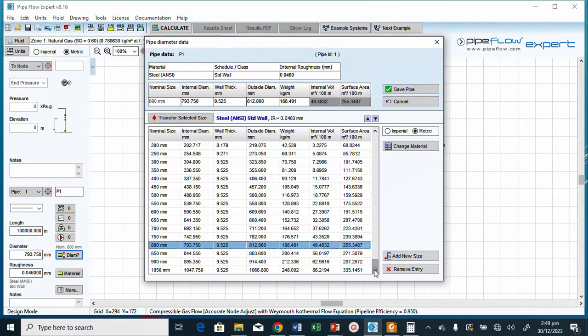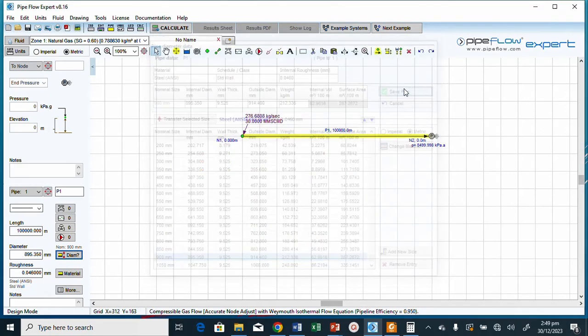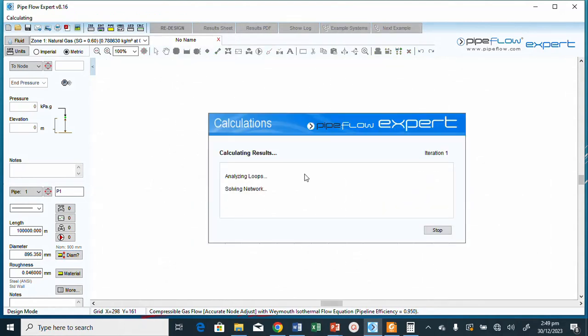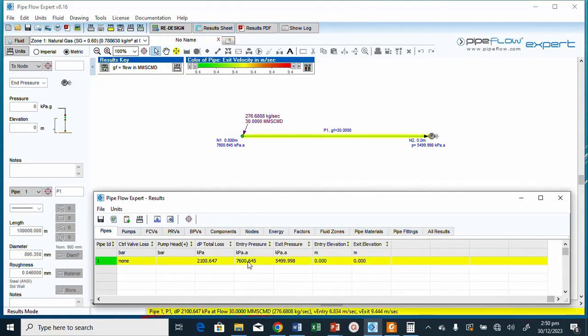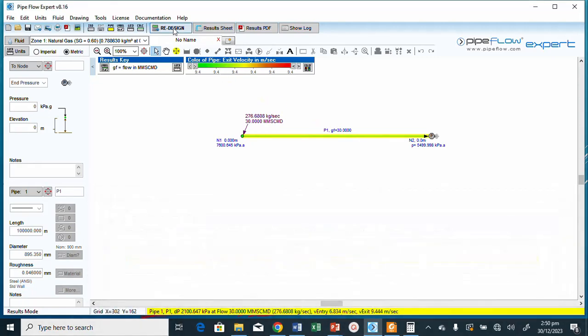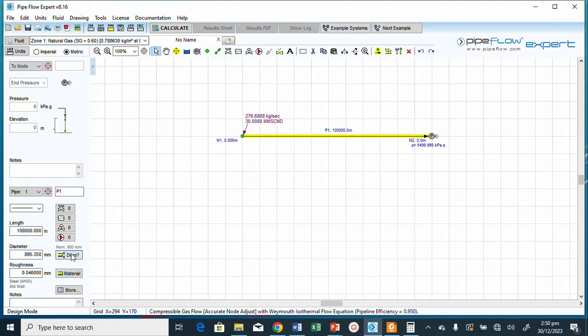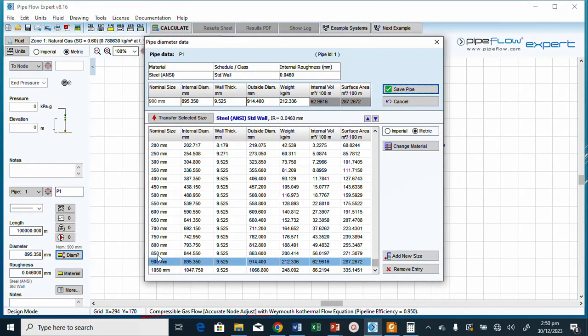With 900 mm, the entry pressure drops to 7600 kPa — now below 8500 kPa, which is too low. So the answer is somewhere between 800 mm and 900 mm. Let's look at smaller pipes in that range.